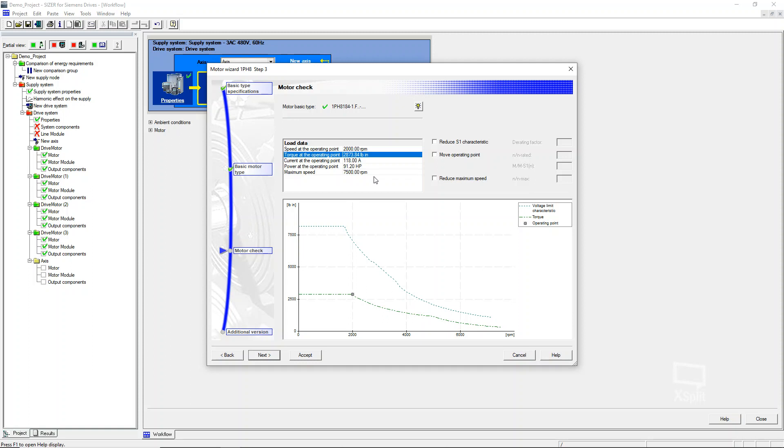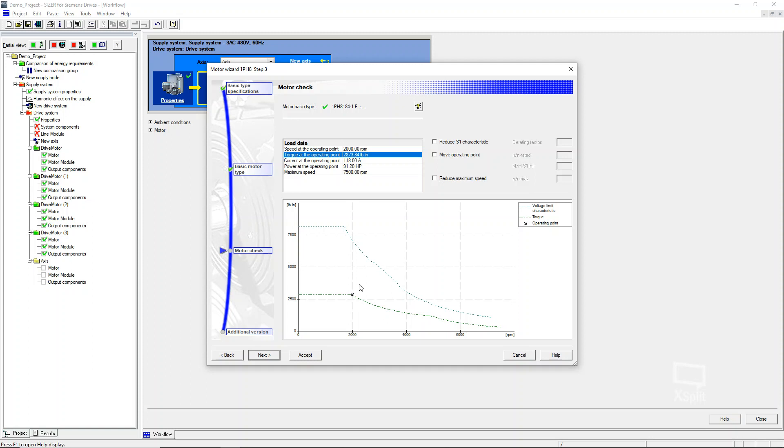What I wanted to show you on this is this is the actual torque curve of this motor. So the maximum speed of this motor is 7,500 RPM. If you look at this data, this torque curve goes all the way down. Now these two lines, the green line down on the bottom is the actual torque curve. And then the blue line is the voltage limited characteristics. So the maximum torque available from this motor. This green line is what is called S1 characteristics, an S1 duty cycle. If it is on or under this curve, this motor will not overheat. It is rated for continuous duty. Now, obviously the speed at the nameplate or the base speed, depending on your terms, is going to be 2000 RPM. And that's what your default nameplate or default operating point is.